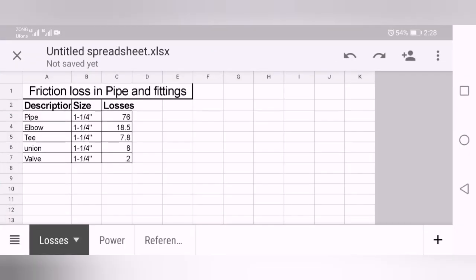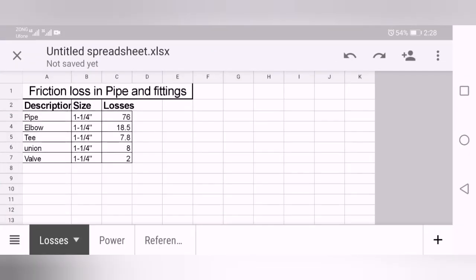You have just to multiply these figures depending on the pipe sizes and note it down. Like I noted down myself, I just created this simple Excel sheet for my office work. Here I'm using one and one-quarter inches of pipe having 76 feet of loss. These units are in feet. An elbow of the same size has 18.5, tee has 7.8, union has 8, and valve has 2.